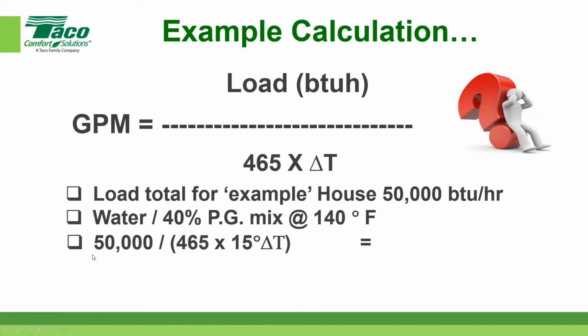And here's how the calculation longhand works. Notice down here we would have brackets, so we're going to do that calculation first. 465 times 15. 15 in this case was my delta T, or my temperature differential that I was going to use for that particular job and that particular application.